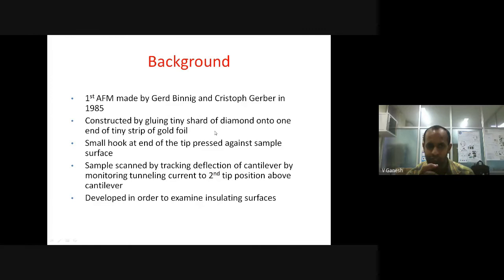In the case of AFM, they use what is called a cantilever, and at the end of the cantilever they attach a probe made of silicon nitride, silica, or diamond. When you bring the cantilever as close as possible to the sample substrate, depending on the intermolecular force of attraction or repulsion between the sample substrate and the probe, the cantilever starts to oscillate - it starts to vibrate. The backside of the cantilever is coated with gold so that one can shine a laser light on top of it. By looking at the intensity of the reflected light using a photodiode, you can correlate the oscillation, and correlate the change in spring constant of the cantilever. That is the basic principle behind atomic force microscopy.